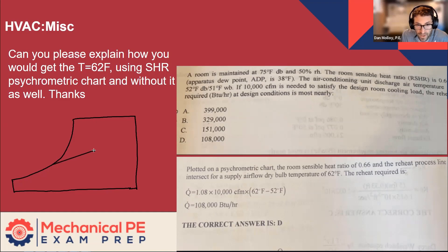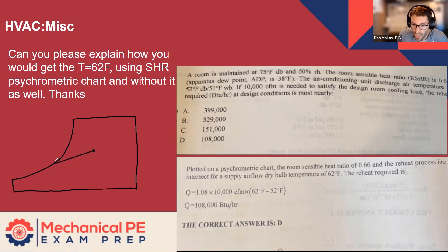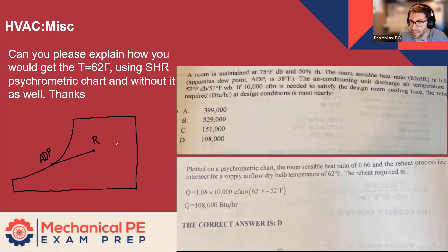We're going to follow some process line for cooling down and to the left — so there's cooling and dehumidification happening — and that's tracking toward a location on the saturation curve that we call the ADP, the apparatus dew point. The slope of that line is dictated by the sensible heat ratio.